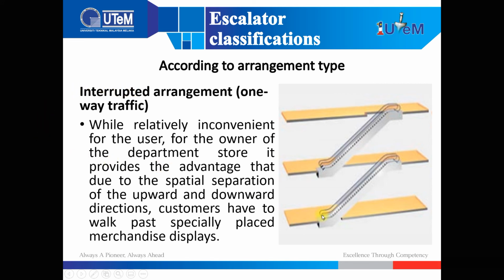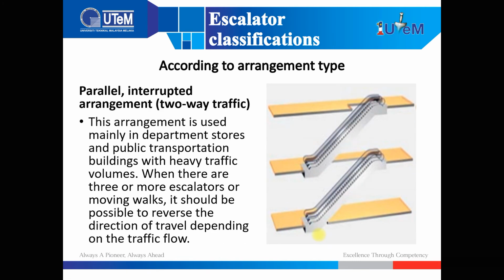Okay, so kita rasa tak convenient, tapi benda ni bagi advantage kepada owner kedai. Okay, untuk parallel interrupted arrangement, this arrangement is used mainly in department stores and public transportation buildings with heavy traffic volume. Okay, untuk heavy traffic volume, dia akan gunakan arrangement jenis yang ni lah. When there are 3 or more escalators or moving walks, it should be possible to reverse the direction of travel depending on the traffic flow. Okay, kalau terlalu ramai, mungkin dua-dua side ni dia akan ambil dua-dua direction lah.